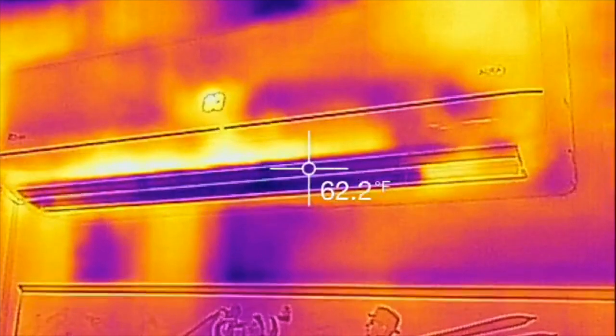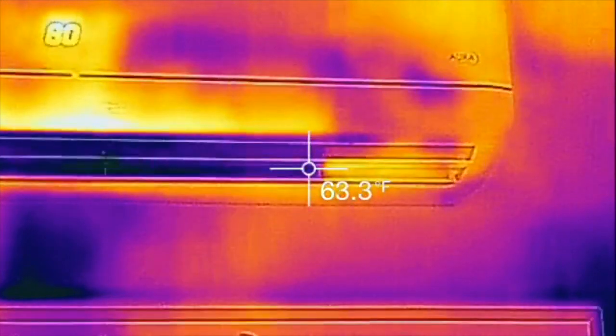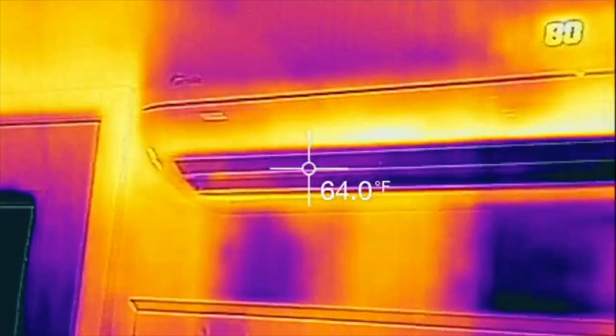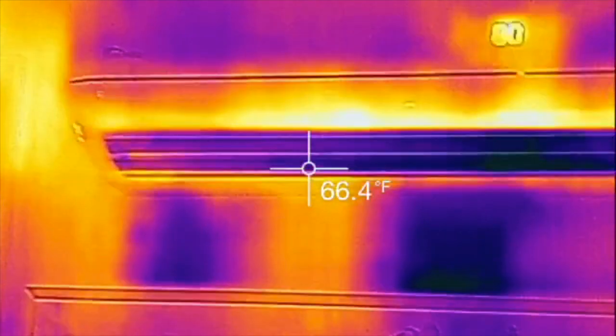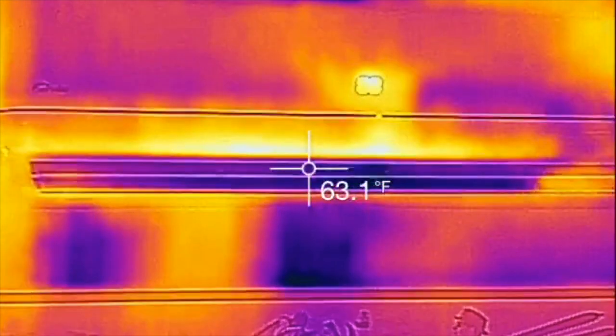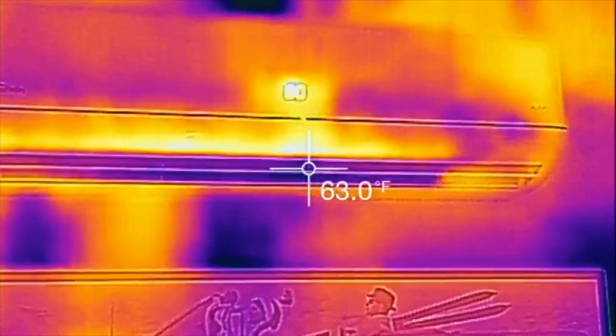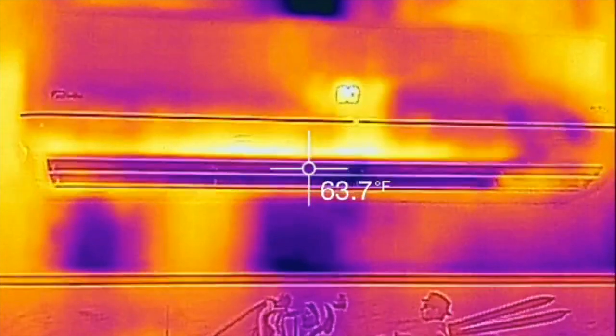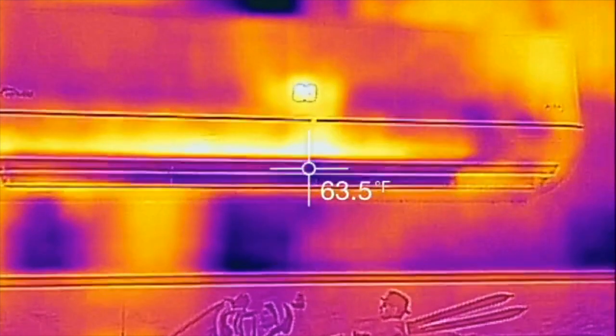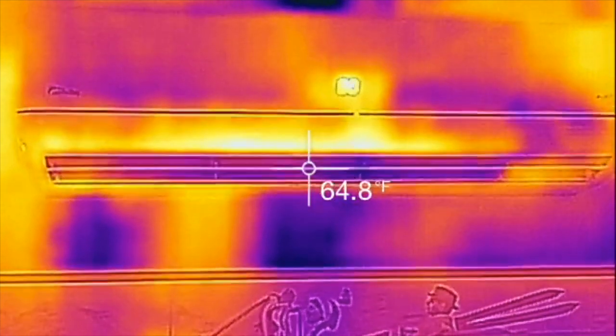This thing just got done wrapping up a defrost cycle. I've noticed that the coil has gone down to even colder than ambient — 62 degrees. I haven't seen this on a thermal camera yet, so this is kind of cool to see. It just got done running the defrost cycle and it looks like it's heating those coils up again. The refrigerant is flowing through the heat exchanger, and yeah, this thing kicks back up to about 95 degrees even when it is negative 27 degrees outside. Just unfreaking believable.